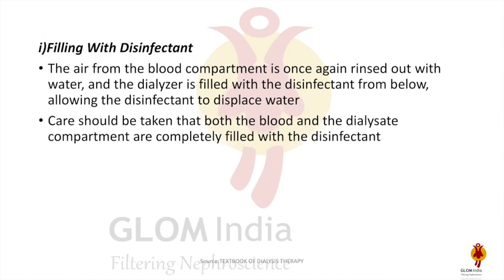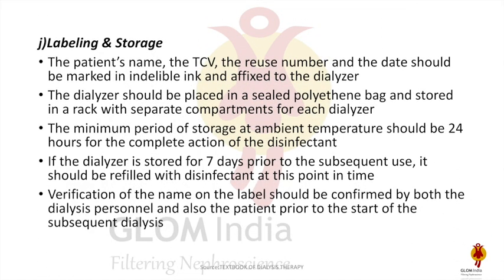For labeling and storage: the patient's name, total cell volume, reuse number, and date should be marked with proper ink, fixed to the dialyzer, and sealed in a polythene bag, then stored in a rack with a separate compartment for each dialyzer. The minimum storage period at ambient temperature should be 24 hours for complete action of the disinfectant. If the dialyzer is stored for more than seven days prior to subsequent use, it should be refilled with disinfectant.